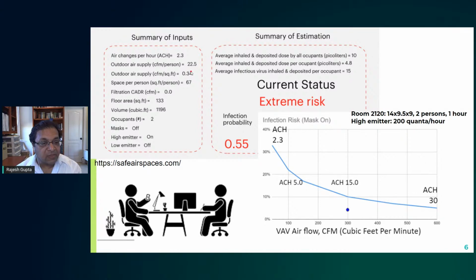Today, when we do infection control, we try to bring it to 1.2. And you have a space per person. This is additional filtration in case you have on the floor filter, and you put those numbers in. It gives you a risk that your probability of getting infected is more than 50%. That's not good for an exposure of 1 hour of meeting in my office.